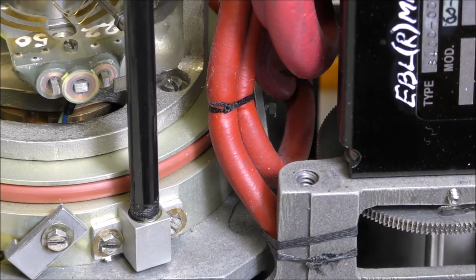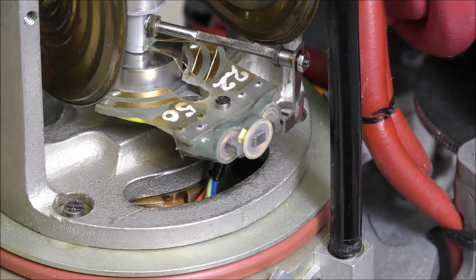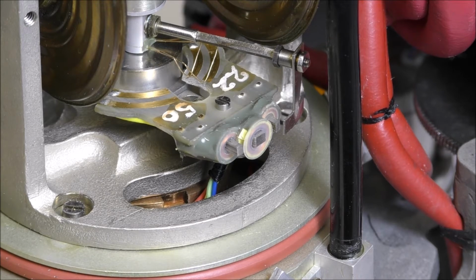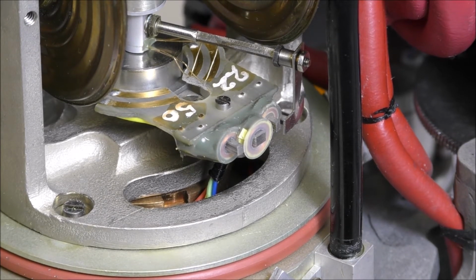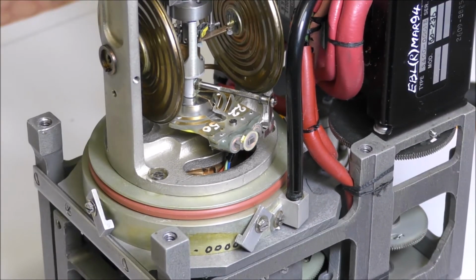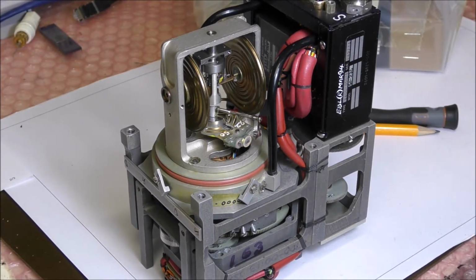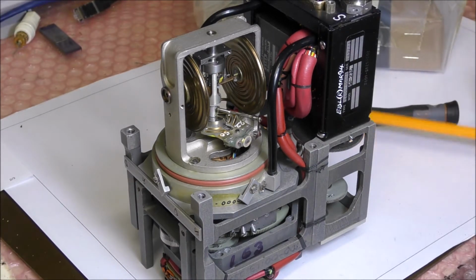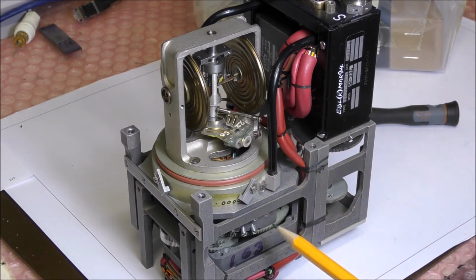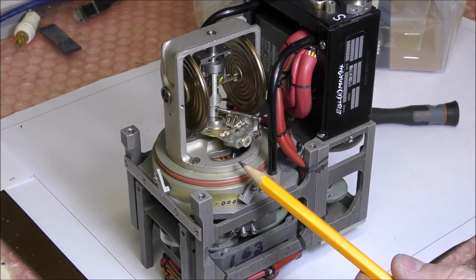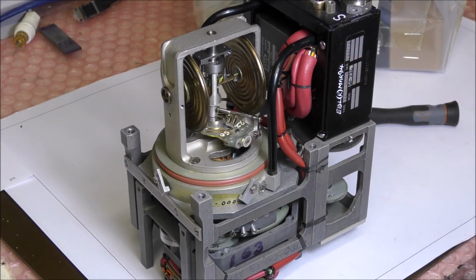Try to zoom on this nice LVDT sensor. Normally there is an amplifier between this LVDT sensor and the AC motor. The amplifier should be inside one of the modules. So the idea is to follow the wires from the LVDT sensor to the modules in order to know which module does the amplification, and maybe there is another module which drives the motor.